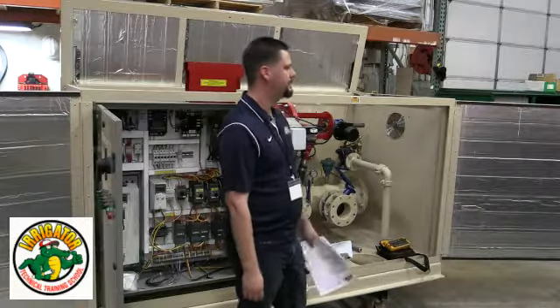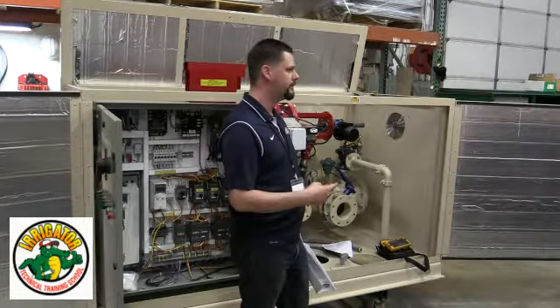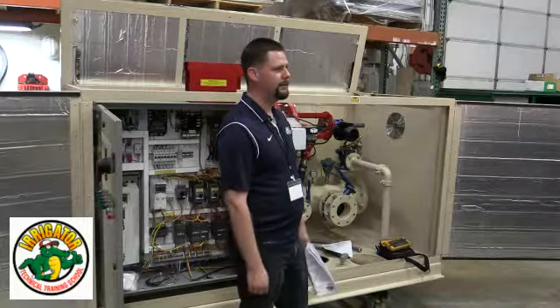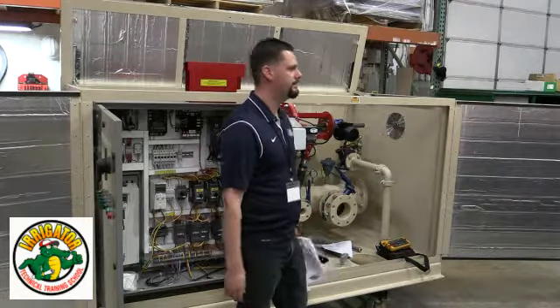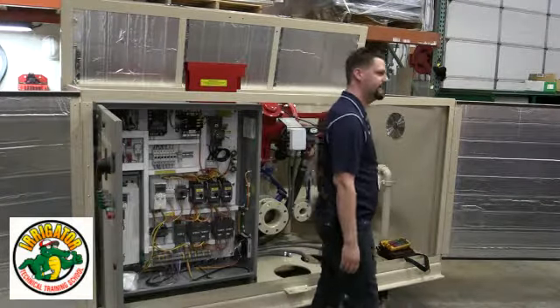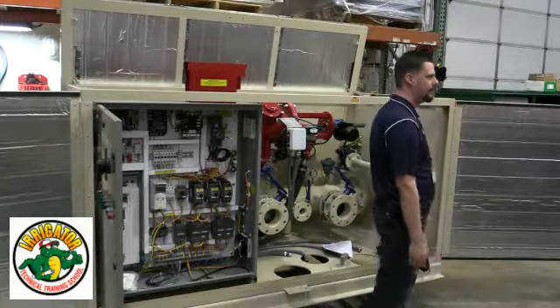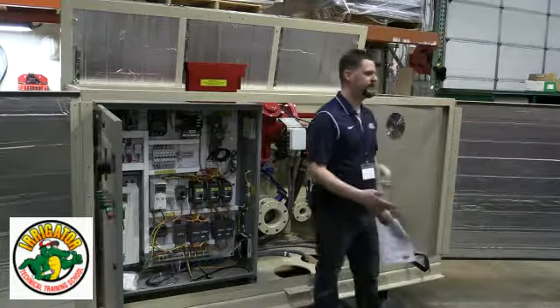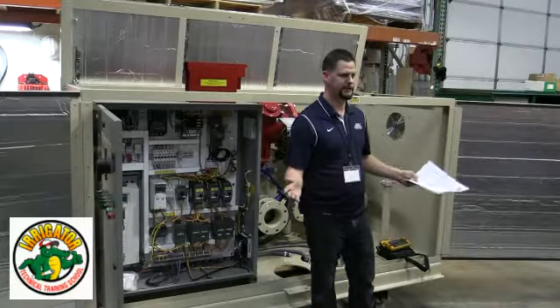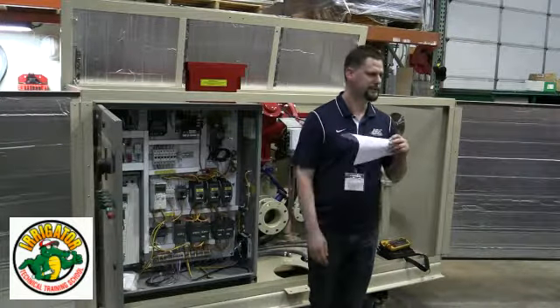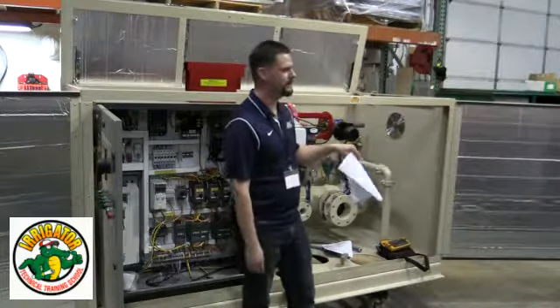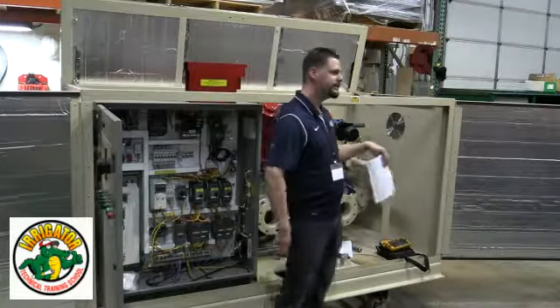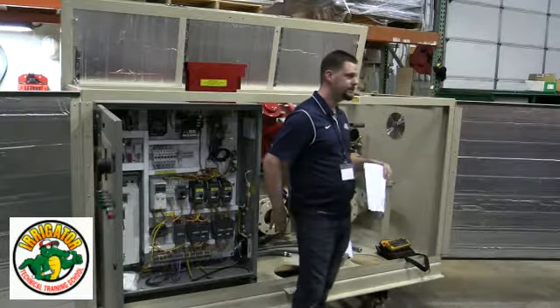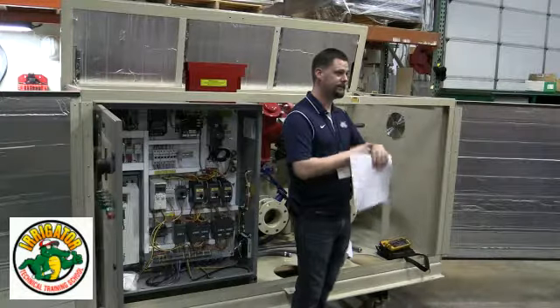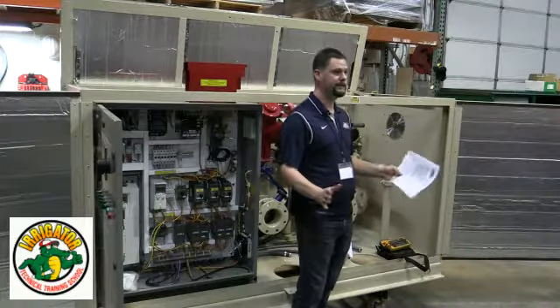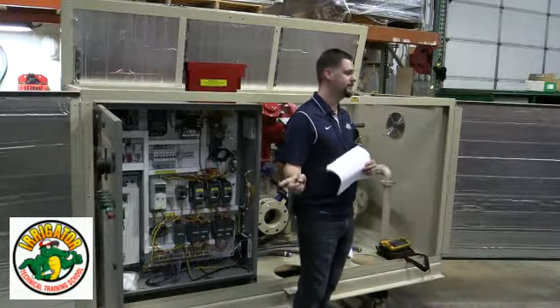It's kind of over pressure, under pressure. Now, under pressure could differ dramatically from one site to another, right? Our standard under pressure, and this is to protect against a main break, is 20 psi for 10 minutes. So if our pump station cannot produce 20 pounds and 10 minutes goes by, it'll shut down on low pressure, assuming there's been a break in the main line.